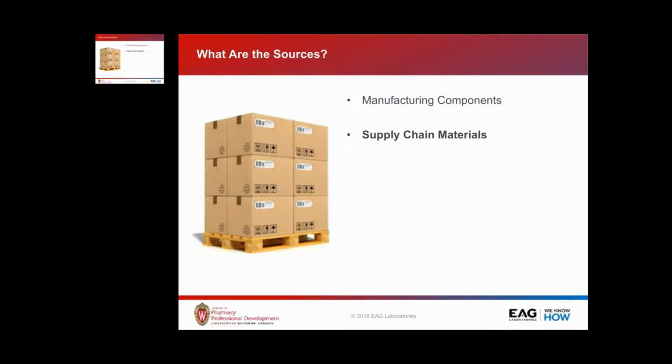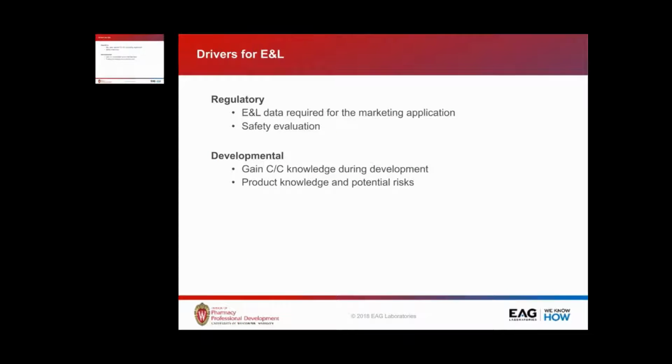So why do we do extractables and leachables? The first is that it is a regulatory expectation. Extractable and leachable data, or at least an assessment of extractables and leachables, is required for marketing applications. It's also required, of course, to be able to perform a safety evaluation. What is being dosed to the patient from a safety concern?